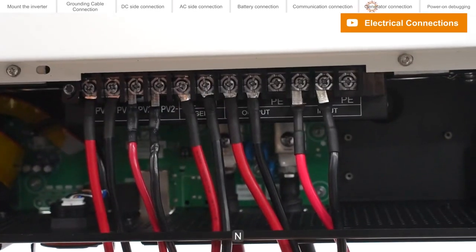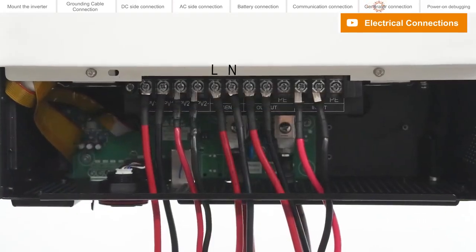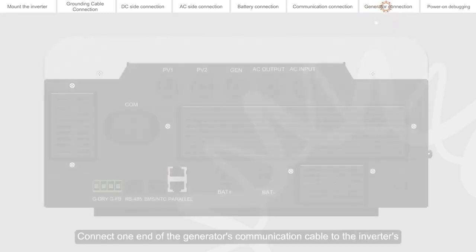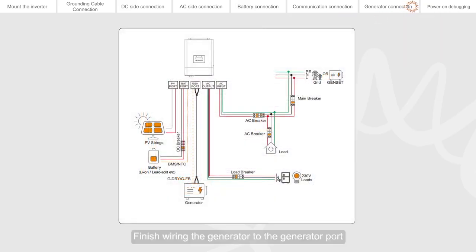Pass one end of the cable through the GEN hole on the bottom of the inverter and connect to the GEN L and N corresponding ports. The other end is connected to the generator. Connect one end of the generator's communication cable to the inverter's G-DRY output dry contact and G-FB input dry contact to control the generator's start or stop. The other end is connected to the corresponding port of the generator. Finish wiring the generator to the generator port.